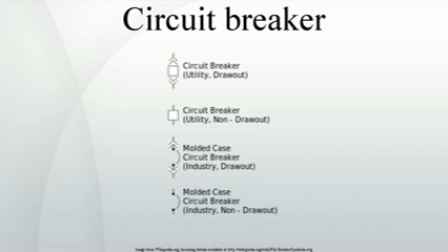Medium voltage circuit breakers. Medium voltage circuit breakers rated between 1 and 72 kV may be assembled into metal enclosed switchgear lineups for indoor use, or may be individual components installed outdoors in a substation. Air-break circuit breakers replaced oil-filled units for indoor applications, but are now themselves being replaced by vacuum circuit breakers, up to about 40.5 kV. Like the high-voltage circuit breakers described below, these are also operated by current-sensing protective relays operated through current transformers. The characteristics of MV breakers are given by international standards such as IEC 62271.